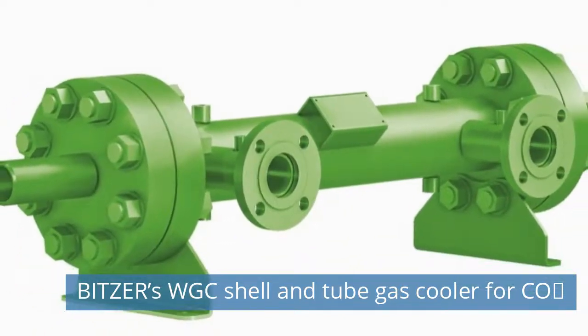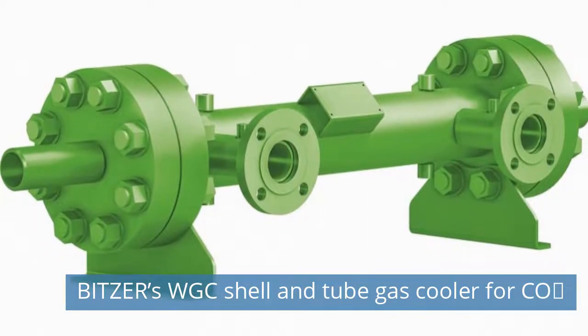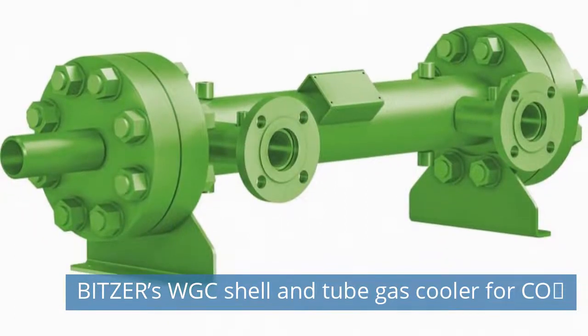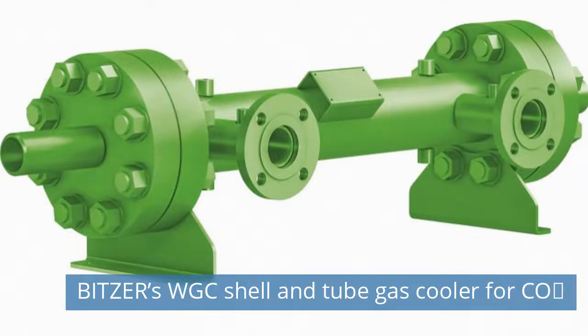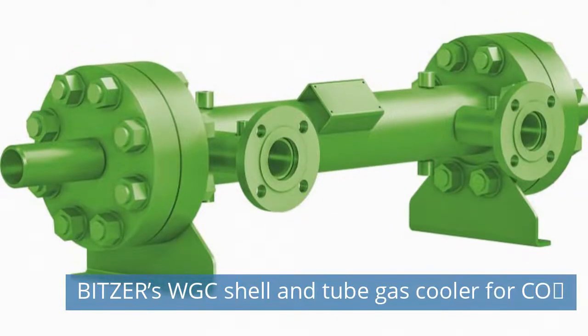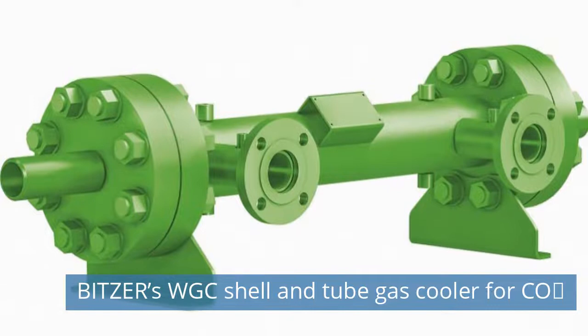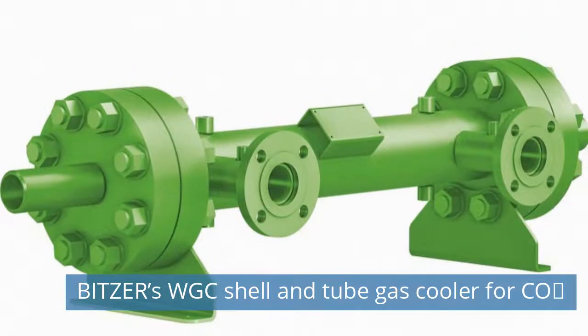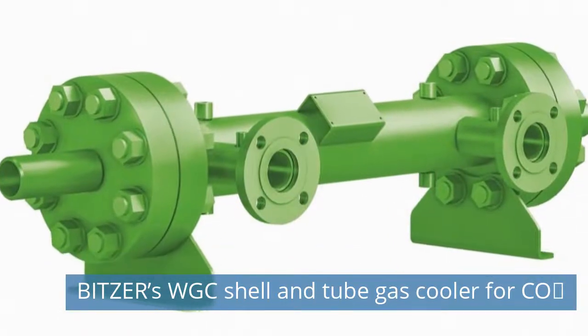BITZER's WGC shell and tube gas cooler, designed for transcritical CO2 applications, has 120 bar design pressure and ensures high resistance to pressure and thermal fatigue. The WGC can be used as a gas cooler, a heat recovery exchanger, and a condenser.